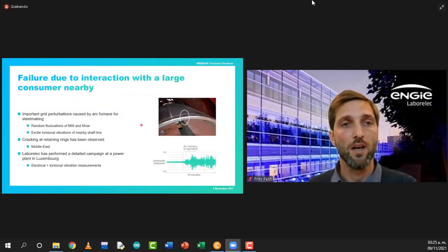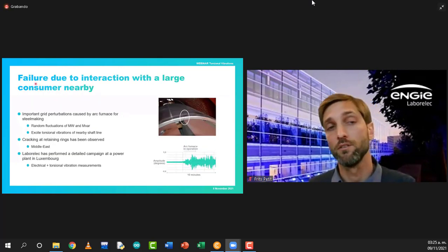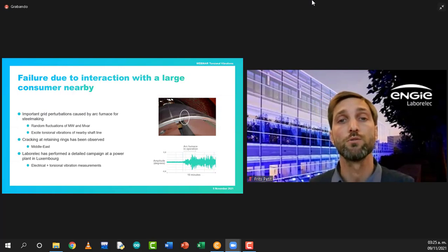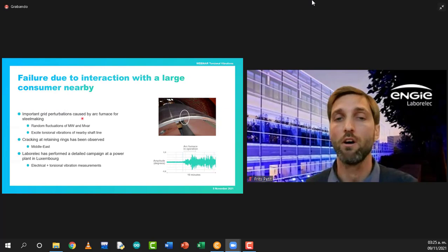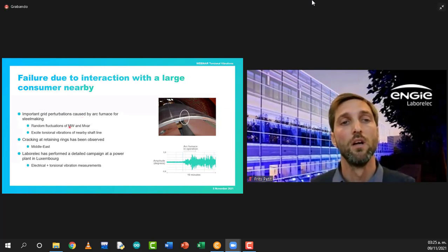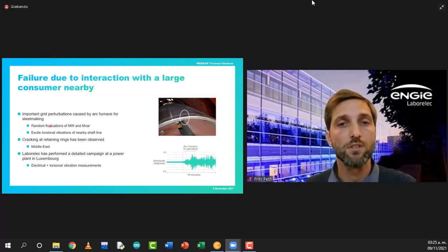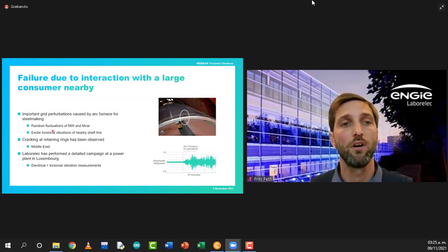And then the last example is a failure due to interaction with a large consumer nearby. As you can see here, a crack was initiated in a retaining ring of the generator due to important grid perturbation caused by an arc furnace for steel making. These arc furnaces typically generate random fluctuations of megawatt and megavar, and then they excite the torsional vibrations of a nearby shaft line.